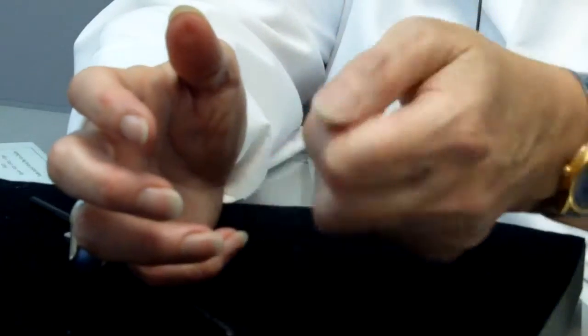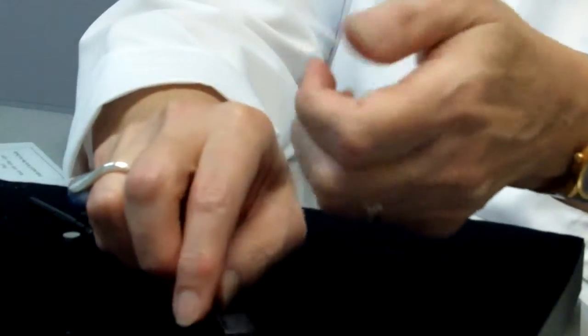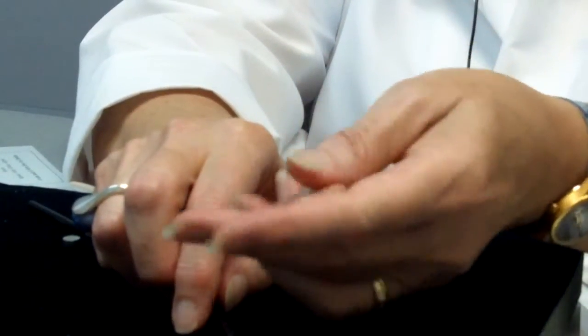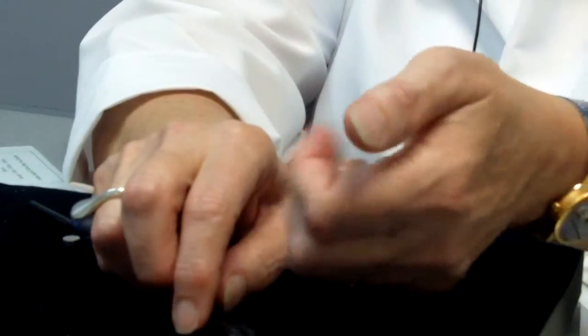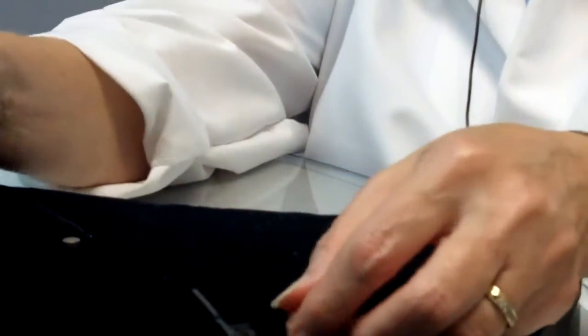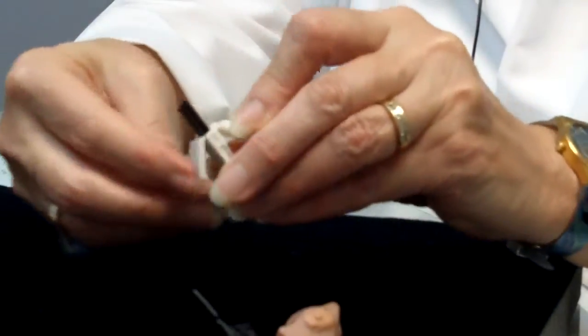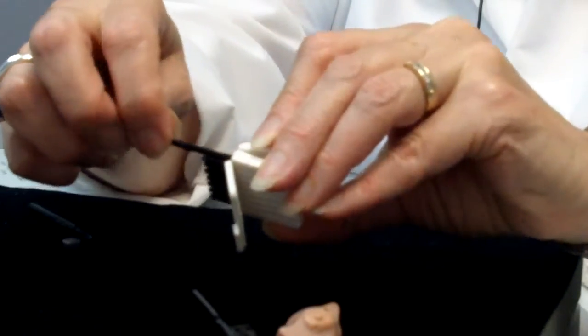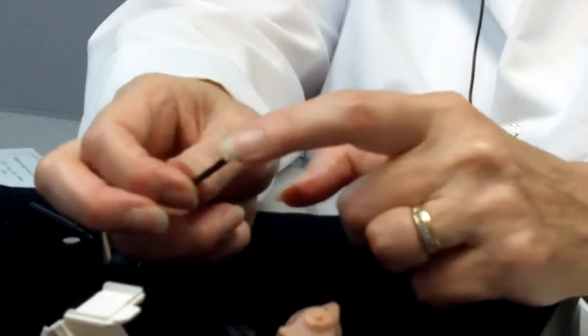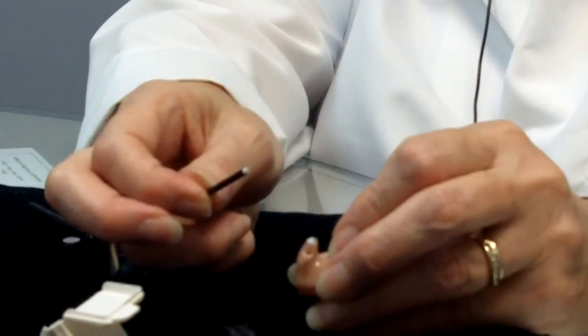Now, at some point, even though you're brushing, the filter is going to get clogged. So if you have a hearing instrument that's custom made with a little white filter, and all of a sudden you can't get the hearing aid to whistle, you've got a new battery in it, you've got it turned on, you've brushed, no whistle, that's called feedback. I'm squeezing it in my hand and causing the sound, forcing the sound back down inside the microphone. You're going to get one of your filters out of the packages we give you. And that's what the inside of that white filter looks like.